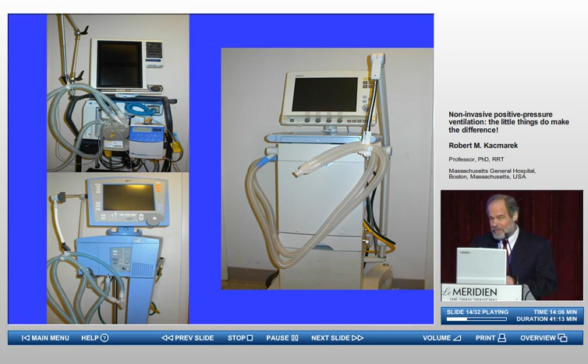Now, that non-invasive ventilation package that exists on these ventilators is very diverse. There is not a consistency across mechanical ventilators. Some of them allow you with this package to turn off alarms that you would not be able to turn off during invasive ventilation. Some will compensate for leaks during triggering to the inspiratory phase. Some will compensate for leaks during cycling to exhalation. Some will compensate for leaks on both sides, triggering and cycling. You really have to look very carefully at what the package provided by the particular mechanical ventilator is to determine how effective that non-invasive ventilation package is on the particular unit that you're using.